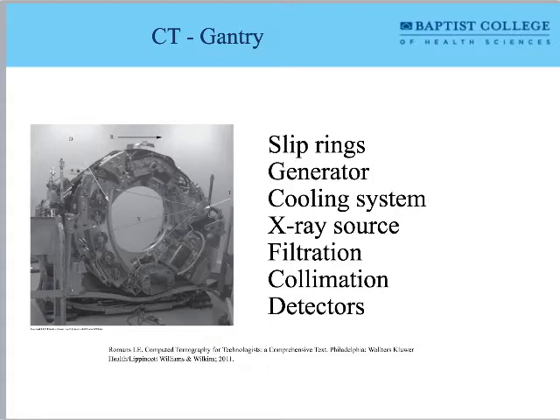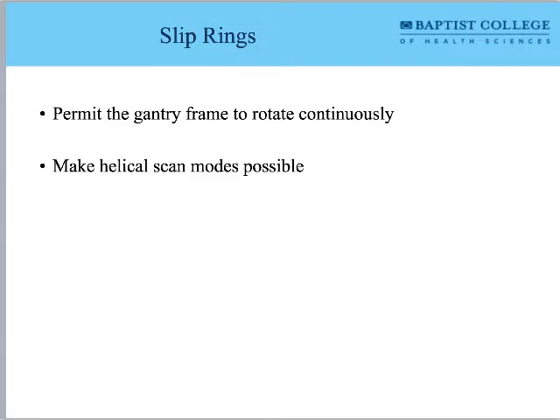On the side of the image receptor, and over here is the x-ray tube — there are almost air-conditioning-type units around it because it produces a tremendous amount of heat. It has filtration systems, collimators, and detectors. This machine uses a fan beam of x-rays. Those divergent lines surround the isocenter — the point around which it's spinning — and it's got this fan of x-rays hitting a curved bank of detectors, which picks up the remnant beam exiting the patient.